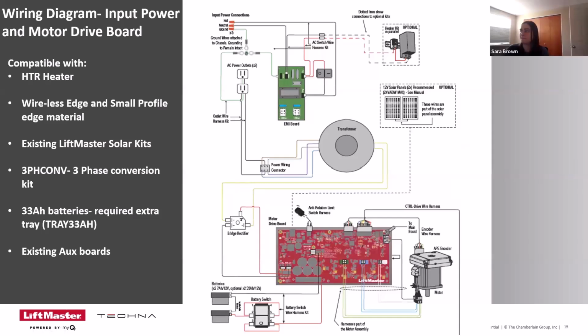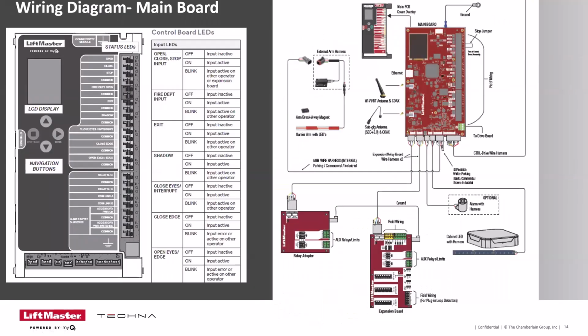What, if any, types of lightning protection are available on this unit? Similar to our other operators, we do test for power surges. If you get a lightning strike and it impacts the operator, it's going to cause the board to fail first before other components. We did do lightning testing, though I don't recall off the top of my head how much energy we put into the system. It does not protect against direct lightning strikes, it basically protects for a lightning strike in the area that causes some type of power surge.